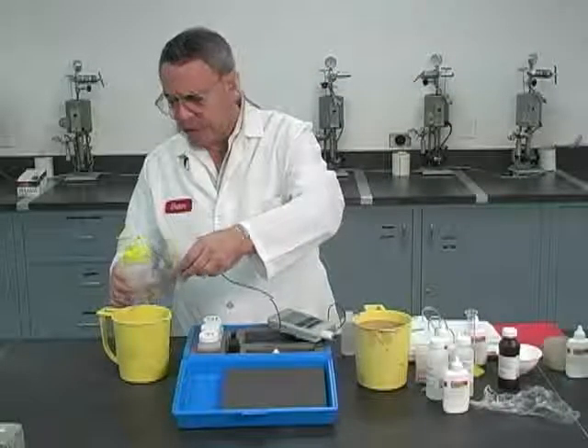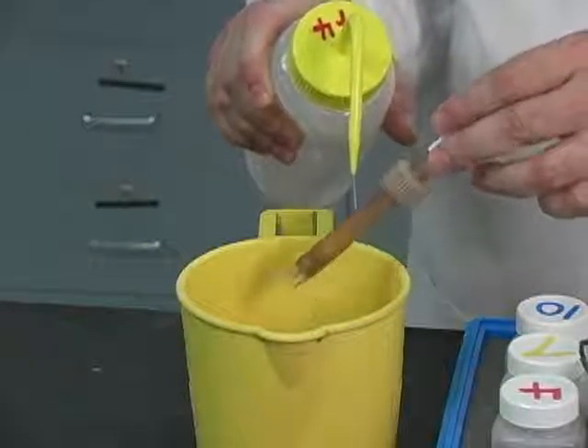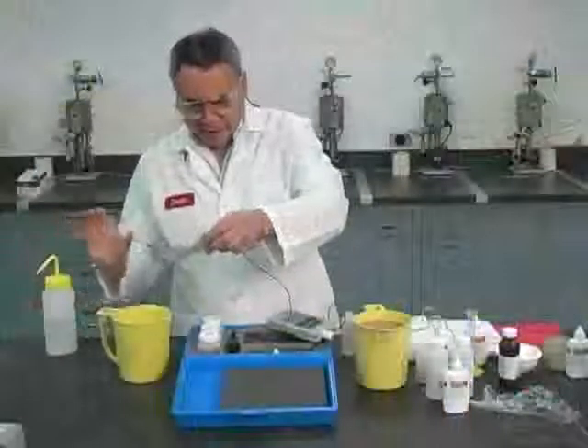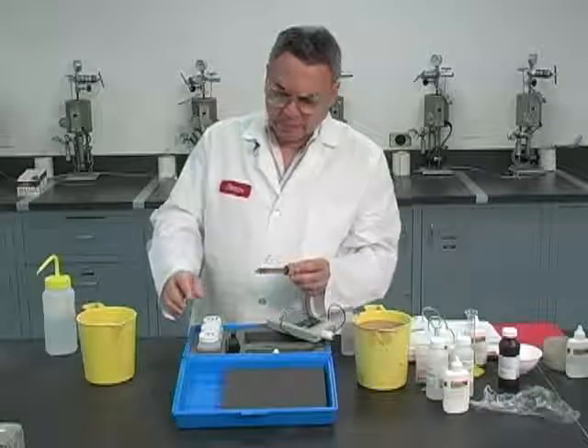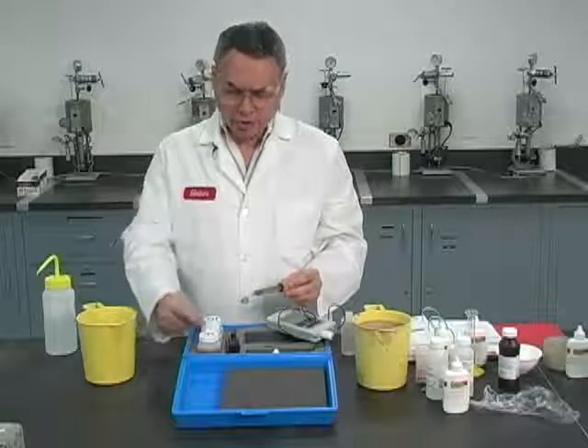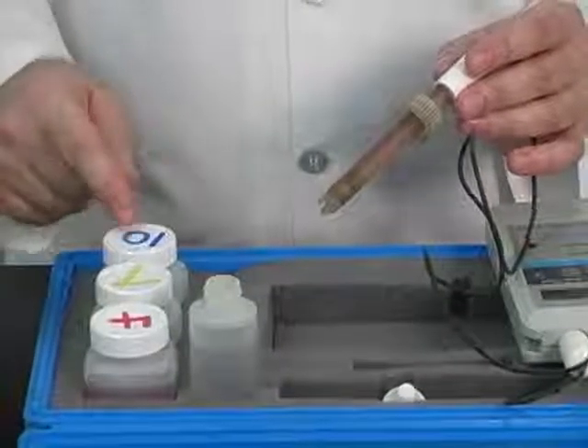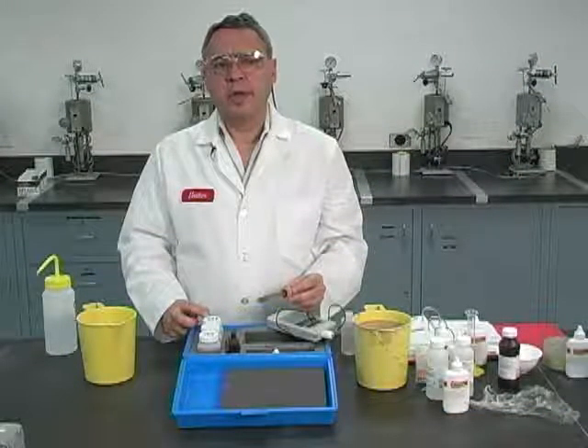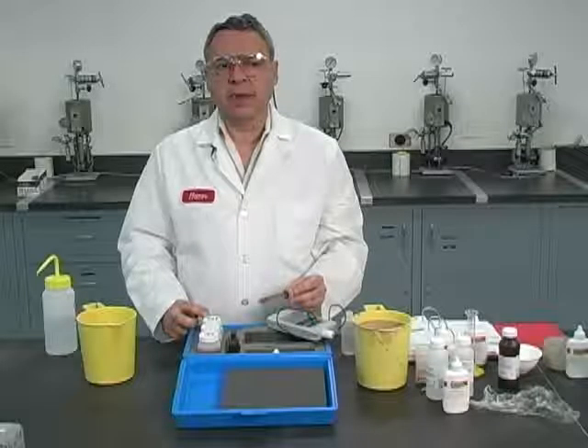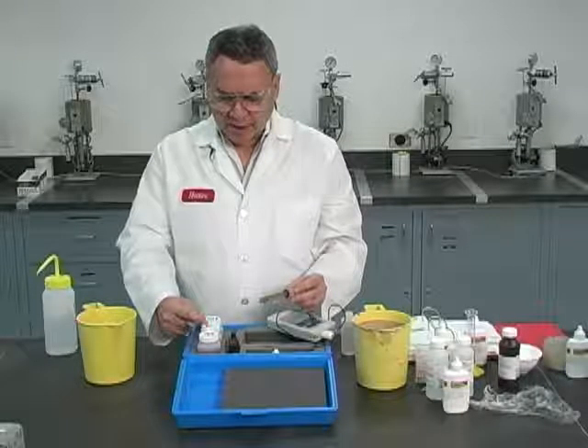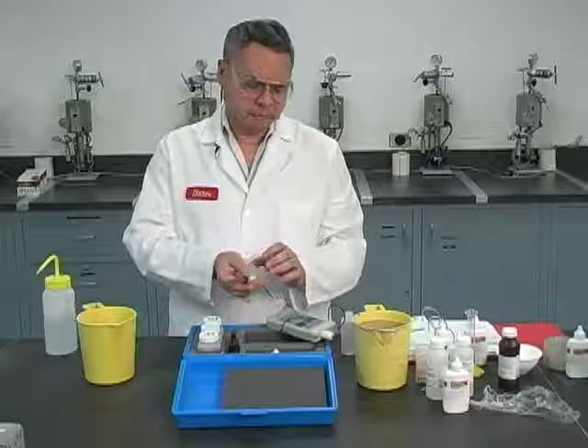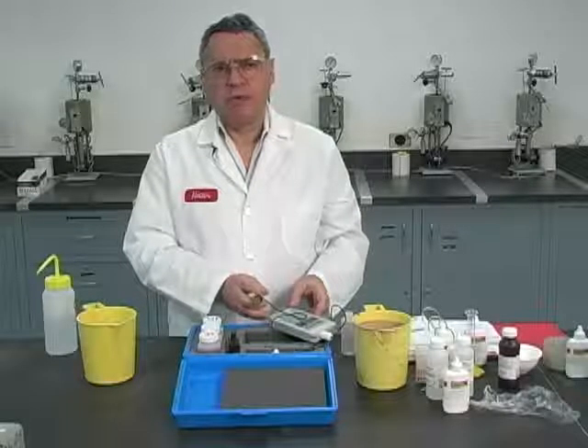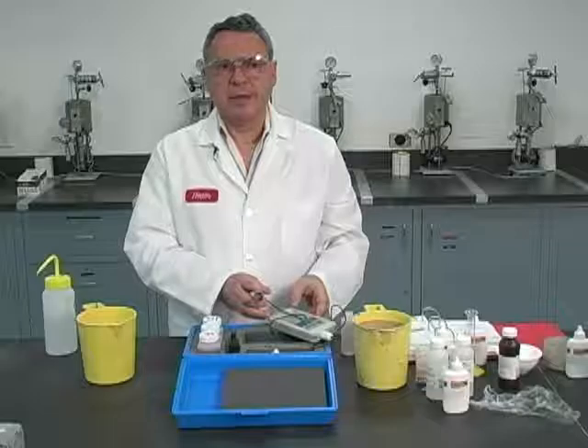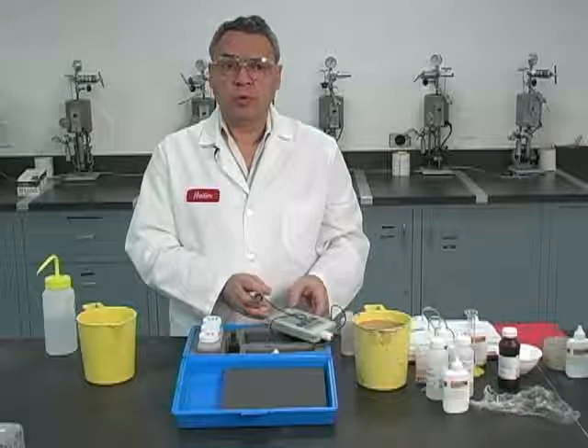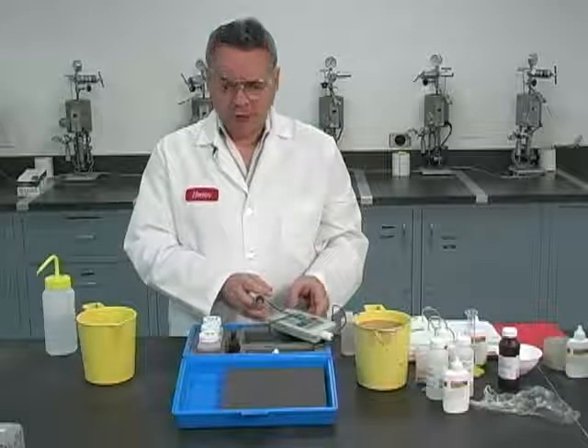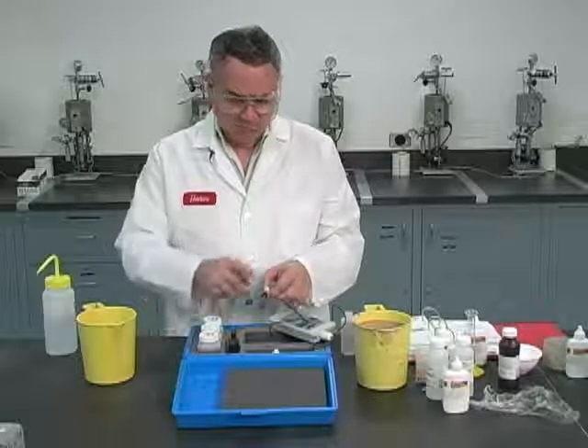I'm careful to make sure that I don't touch anything inside this particular cylinder. I have in this box buffer solutions, pH 4, pH 7, pH 10. Because I'm going to be working in a range which is going to be above 7, all I need to do is calibrate for 7 and for 10 in this particular mud. Some fluids might require something different. For example, a zinc bromide, highly concentrated solution will have a pH below 7, then we would have to calibrate it between 7 and 4.